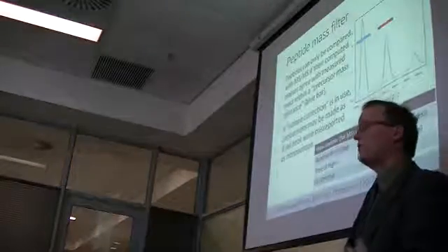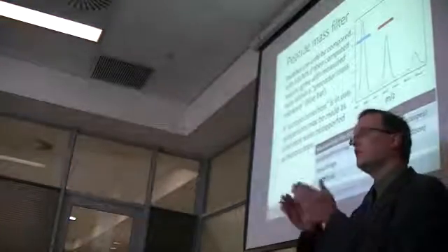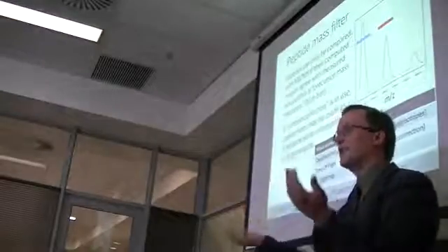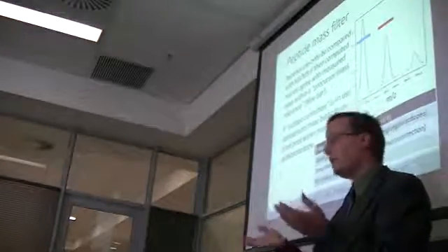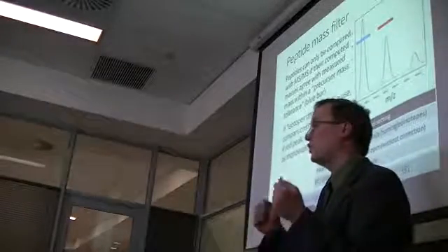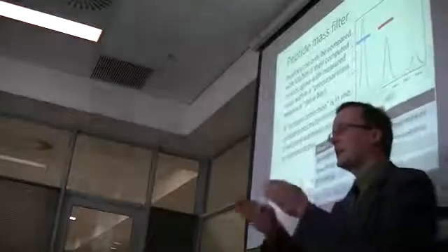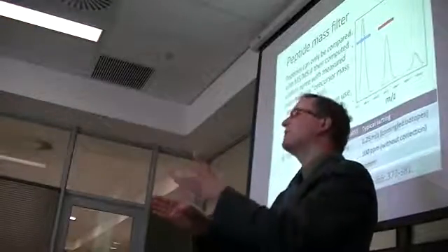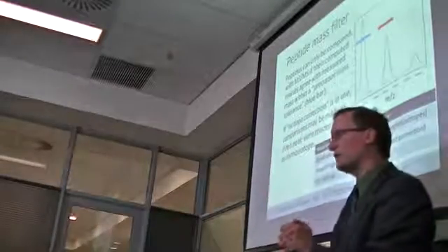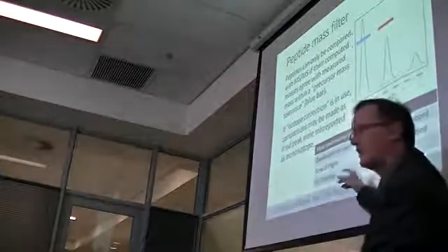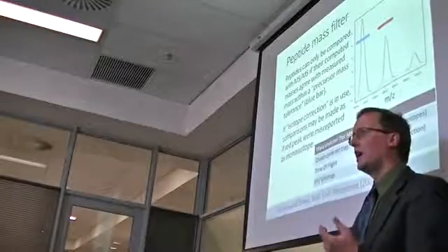So a time of flight mass analyzer sits somewhere in the middle of the mass analyzers we have available to us. Kind of the venerable and still widely used mass analyzer, the quadrupole ion trap, has what we call unit resolution. We can tell within a mass unit how heavy something is as it moves around in a quadrupole ion trap. In a time of flight mass analyzer, we're sitting somewhere in the middle.